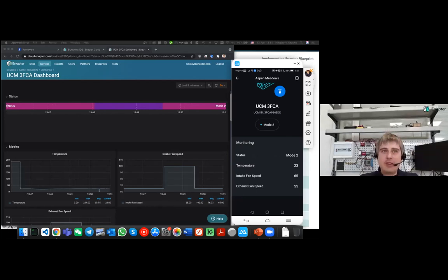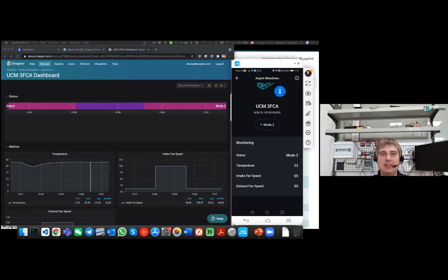The reason is simple: this ventilation system has a rotary heat exchanger. In-house air, around 21 degrees, goes through the heat exchanger, takes the heat, and preheats the incoming air. But it read 28 because the system was stopped and it's insulated very well. We stopped the fans, so the air wasn't going back and forth, and that's why it rose up to 28 degrees.